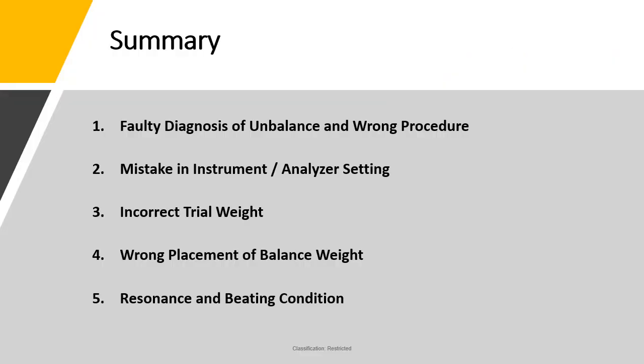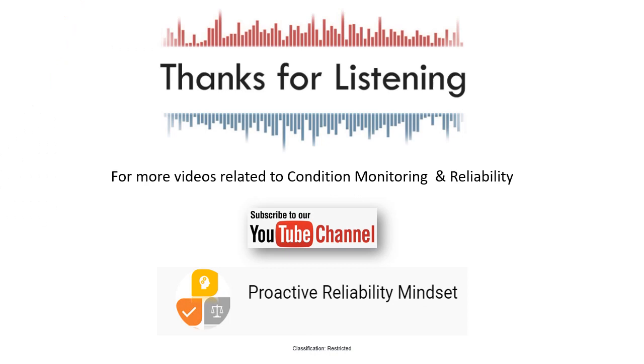To summarize, the five reasons why balancing can fail in the field are: first, false diagnosis of unbalance and wrong procedure; second, mistakes in instrument or analyzer settings; third, incorrect trial weight; fourth, wrong placement of balance weights; and fifth, resonance and beating conditions. Understanding and avoiding these mistakes will help you succeed in your next balancing job. Thank you for your time — for more videos on condition monitoring and reliability, please subscribe to the YouTube channel Proactive Reliability Mindset.